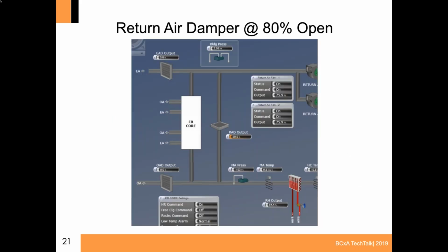So our first position to override the damper, you can see how the damper output is now changed to 80% and it's orange and indicates that it's an override. You want to see what that effect is going to be. And you may wonder how we came up with 80%.